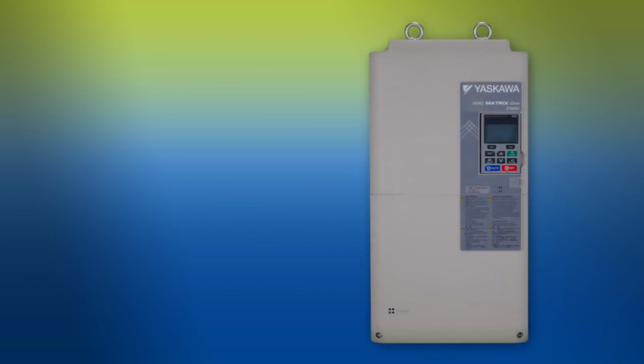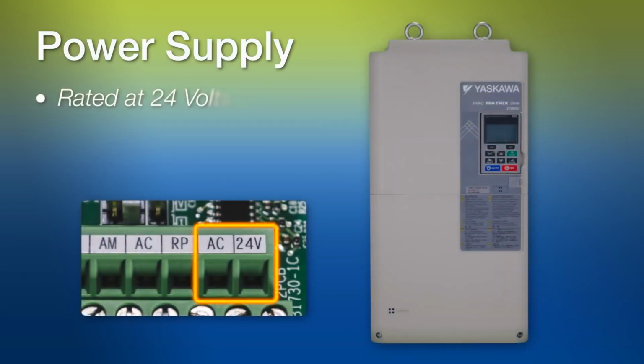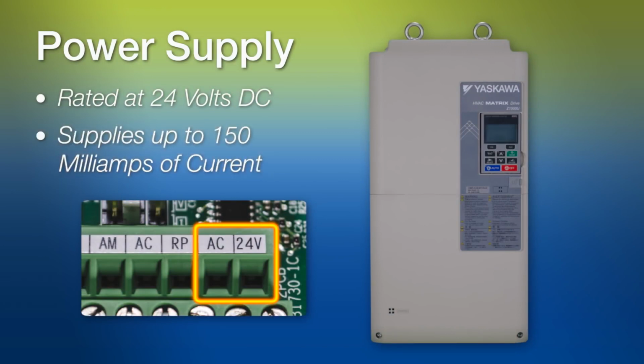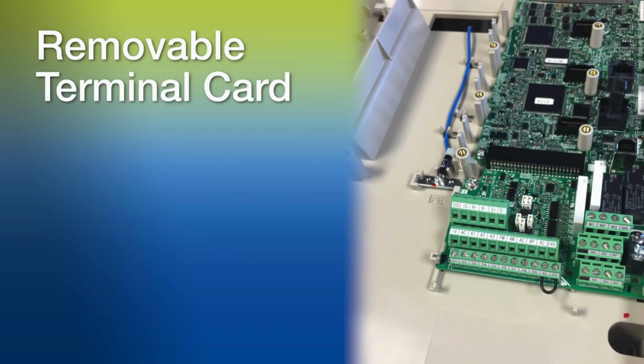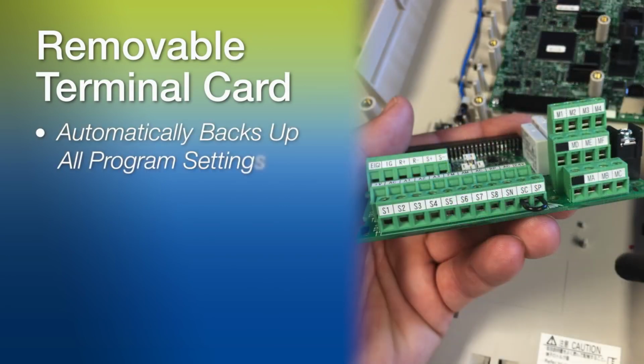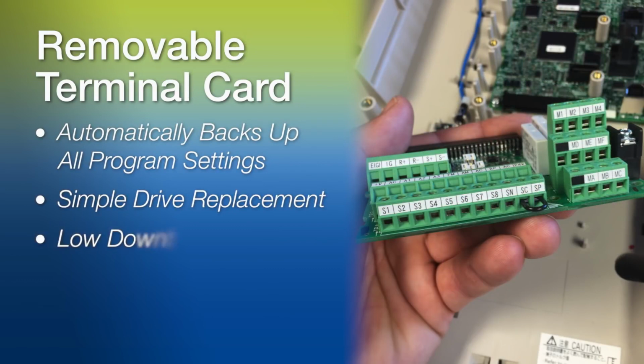Built into the Z1000U is a power supply rated at 24 volts DC and able to supply up to 150 milliamps of current. This is typically more than enough for any customer use for powering transducers and transmitters, eliminating the need for an external third-party power source. The removable terminal card automatically backs up all of your program settings, making drive replacement simple and keeping downtime low.